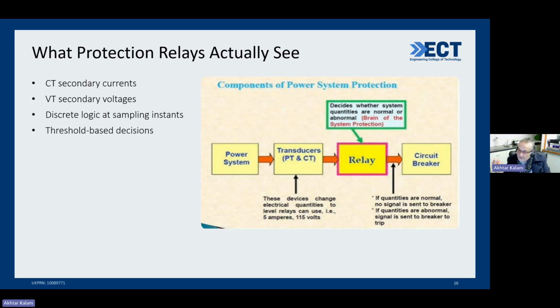The protection relay is rated at 110 volts and 5 amps or 1 amp. In the actual industry, I was talking about an 11 kV system. You talk about a 200 kV system, you talk about a 400 kV system, whatever system you want. You have to bring it down to 110 volts or 1 amp or 5 amps, because that is how the rating is. So you have to step it down. How do you step it down? You use a current transformer and a voltage transformer. So if there is current, there is voltage, bring it down to the level of the protection system that you have.